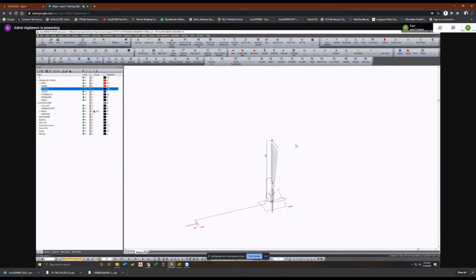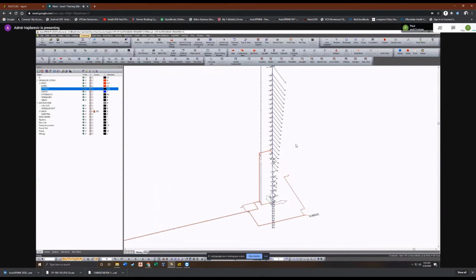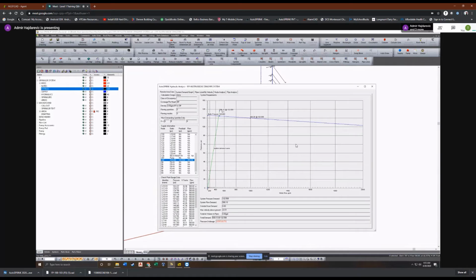There's a lot of friction loss or something like that. We usually don't include those in our calcs ever. I never have. Is there any way to not have the program do that automatically? That's the Standpipe Wizard, I guess you can't. Okay, so those two things made a huge difference. Now instead of 33.5 psi needed, we're down to just under 9 psi, but we are still over the curve.